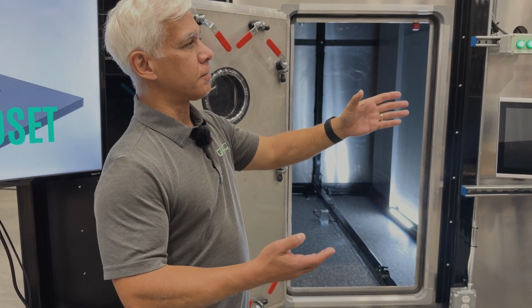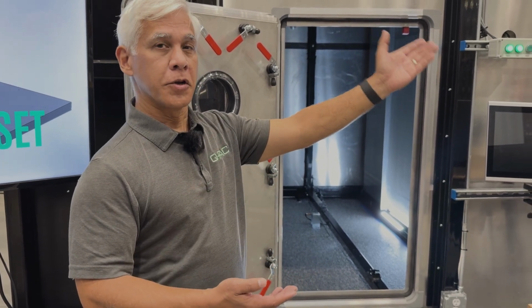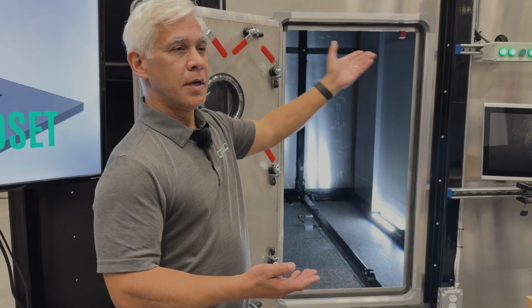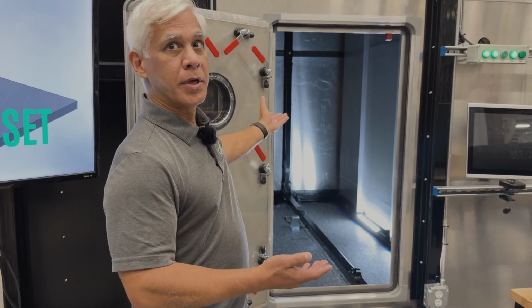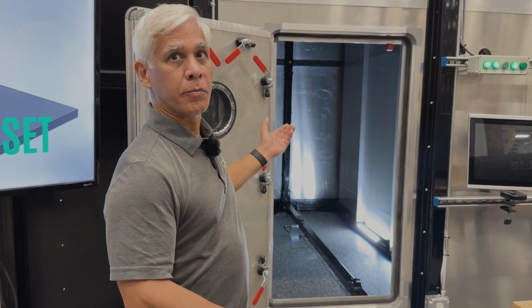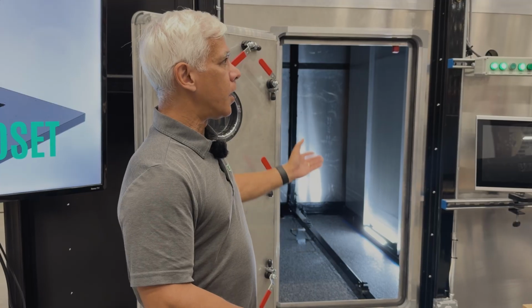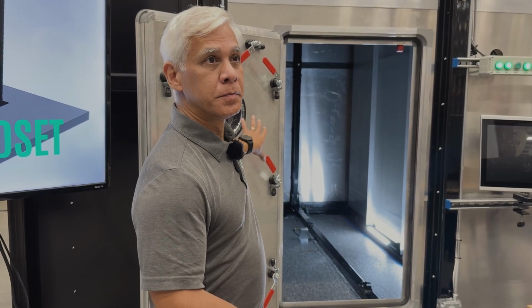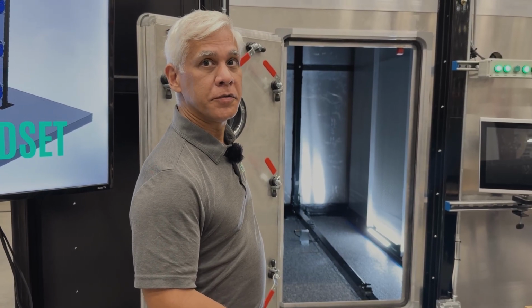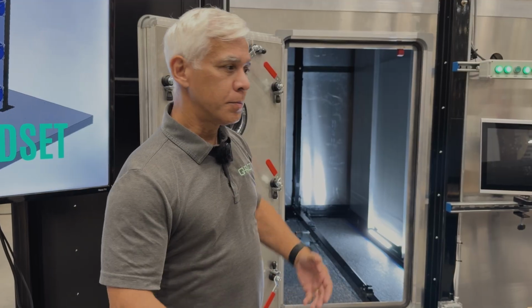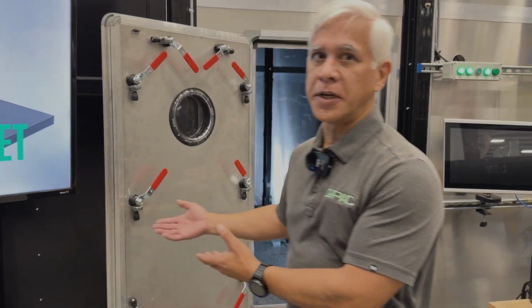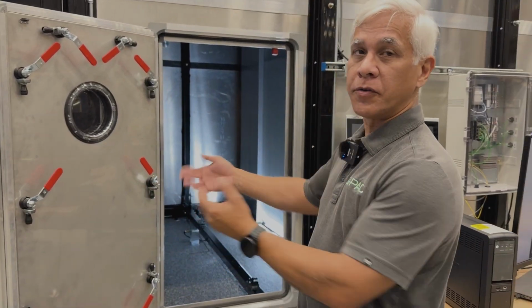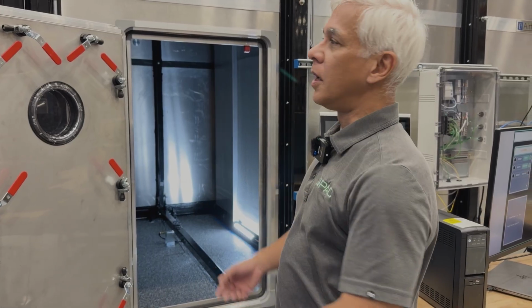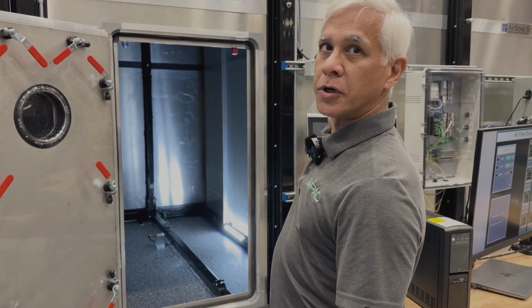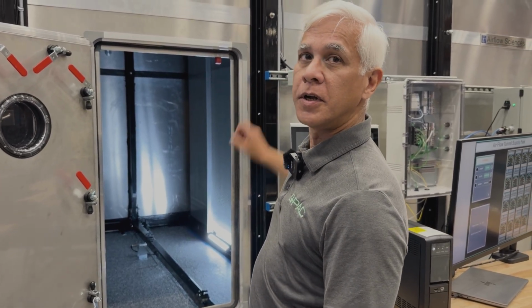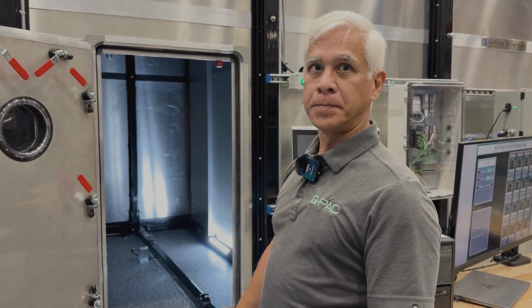And if the only control we have on that end is speed, then we have to be able to control either the airflow or the pressure some other way. And what we do is control the airflow by adding or reducing fans on this side. So that's why you have these fans. So basically, supply makeup air and overcome the resistance of the tunnel to get to the pressure and airflow speed we need for the duty point we're trying to test out. Cool.